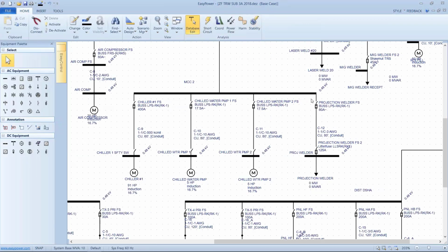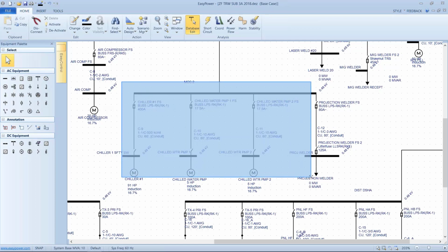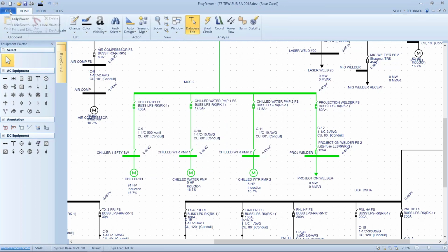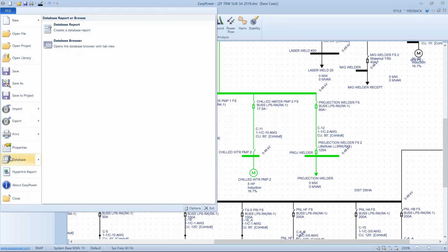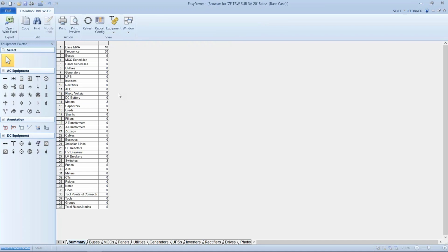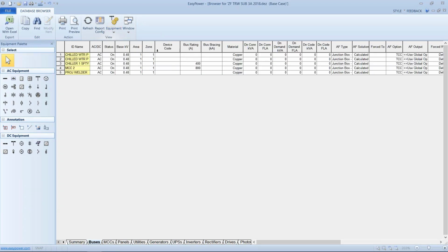Well, to that extent, and we saw this as I opened up the motor control center, there wasn't a rating on that particular bus. Again, I'm going to isolate on this particular part of the system. I'm going to go to the database browser and look at, of these 5 buses that I've included, a selection of some of these elements. If I look at the buses, this shows me right away that none of the selected buses that I've designated have any bracing numbers entered, and these are what are used in comparing equipment duty.